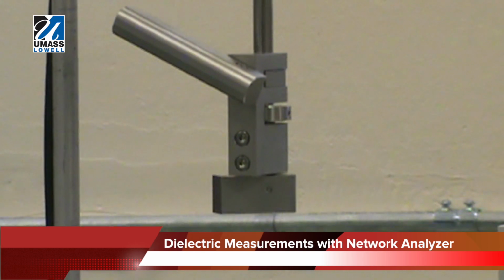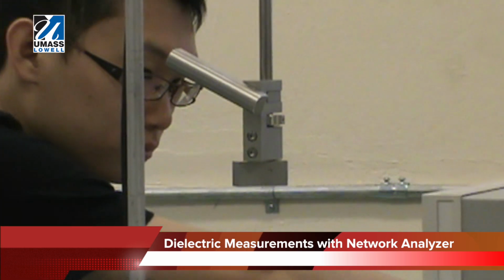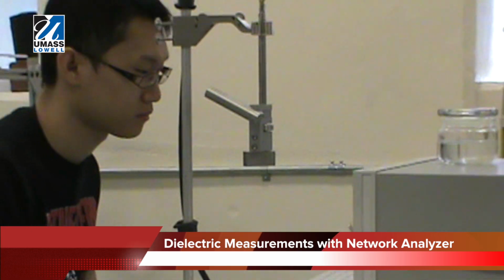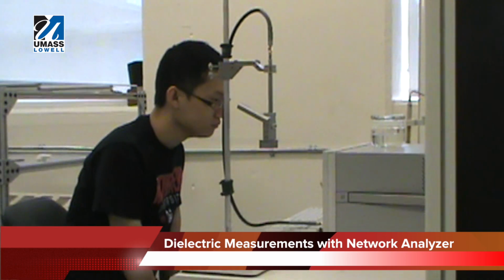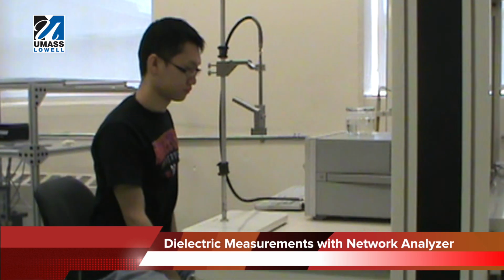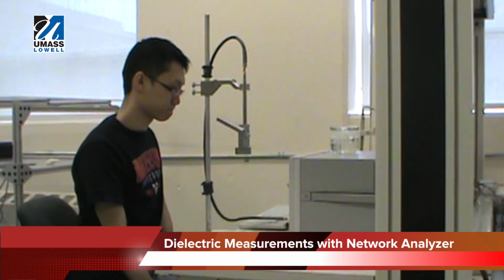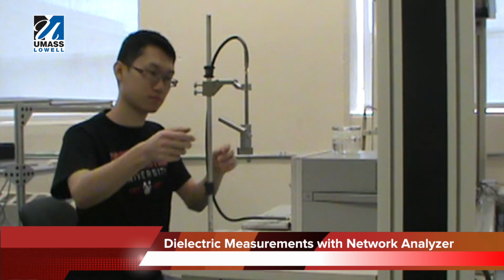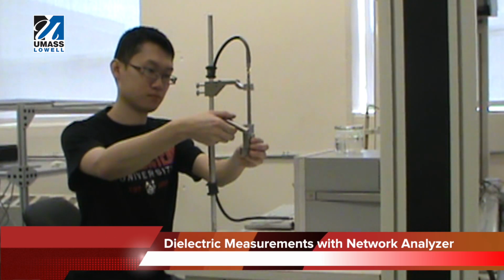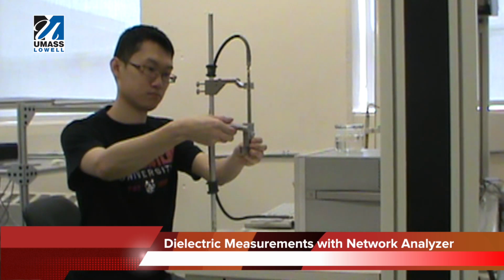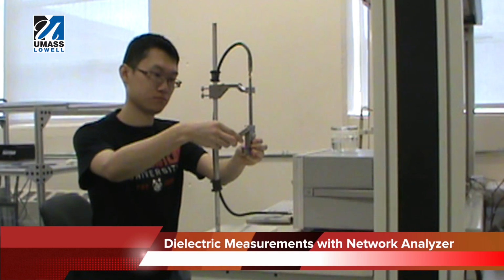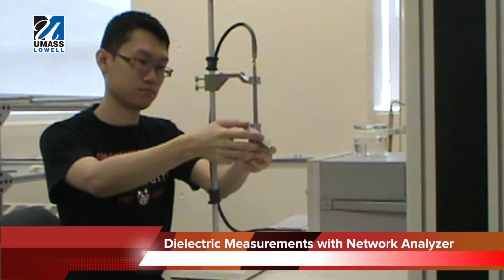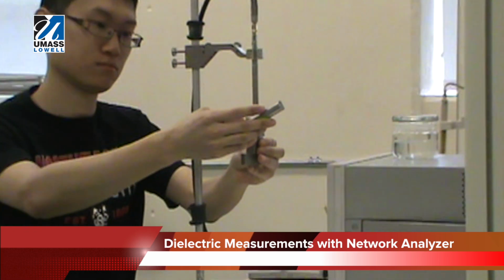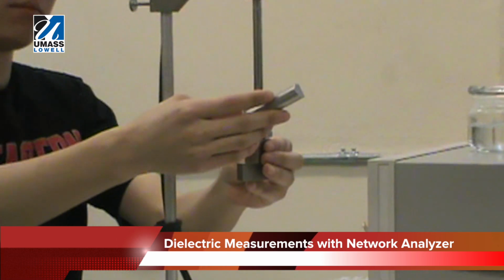In this video, you can see how the analyst is calibrating the network analyzer along with a coaxial probe that we are utilizing for taking the dielectric measurements. The equipment we are using is an Agilent E5071C network analyzer, which has a range of 0.1 MHz to 4.5 GHz. It measures the dielectric property over frequency, and we can get the complex electric permittivity of the material.